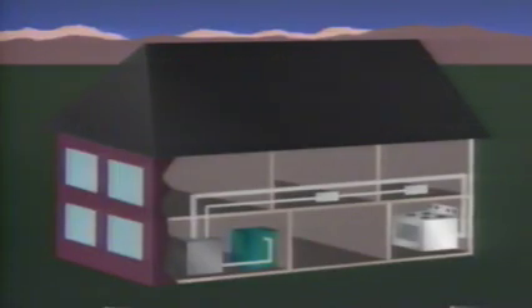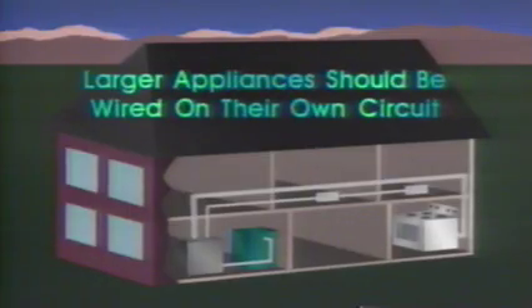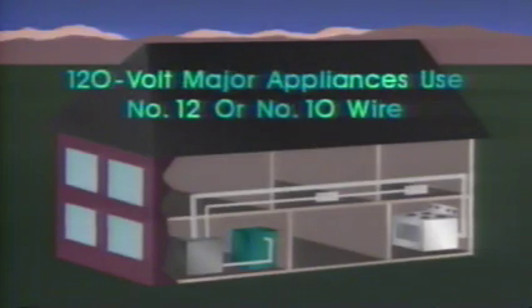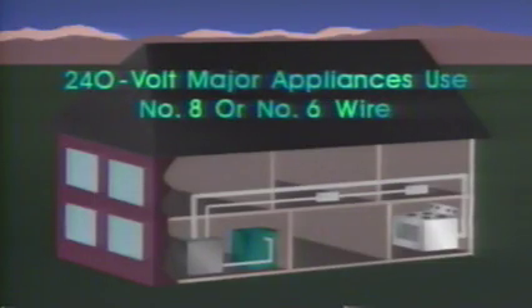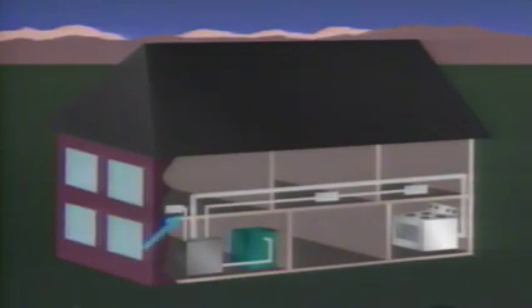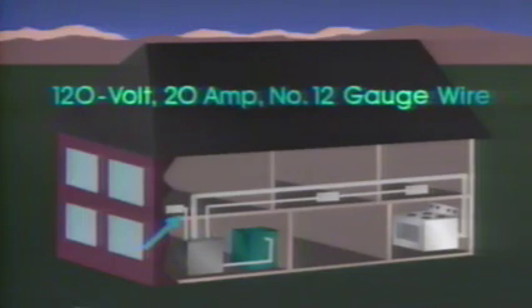Usually appliances like oil burners, boilers, water heaters, washers and dryers, and ranges are wired on their own circuit, with the size of the wire dependent on the amount of electricity the appliance requires. Usually, these major 120-volt appliances will require number 12 or number 10 wire, while the 240-volt equipment will use either number 8 or number 6. Remember, new general residential circuits will usually be 120-volt, 20-amp, number 12 gauge lines.